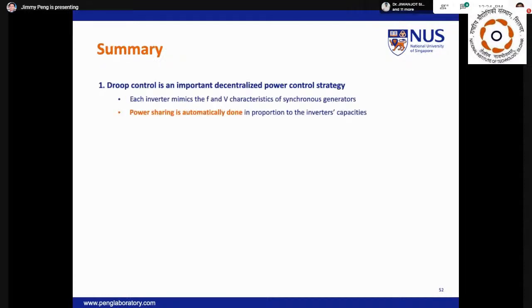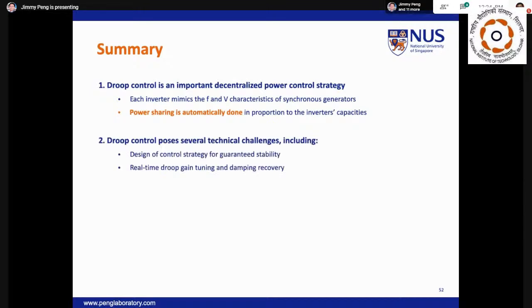So this comes to the conclusion of today's seminar, which can be summarized as follows. Power sharing is an important function among inverter-based generators within the microgrid. When the microgrid is operating in autonomous mode and adopting a decentralized approach to manage its generation, then the stability of the microgrid may be compromised by inadequate Droop settings. In essence, Droop control is used to provide inverters with the ability to regulate the voltage and frequency in the absence of the main grid.